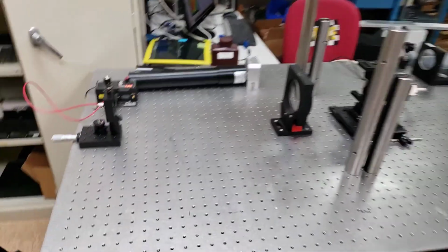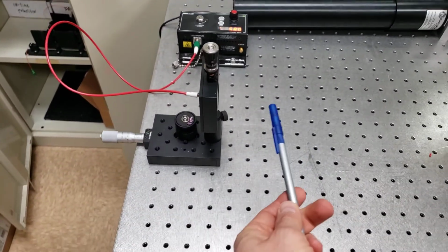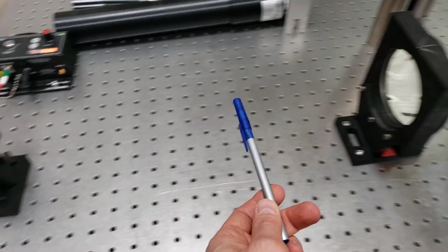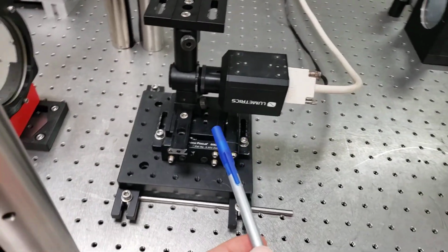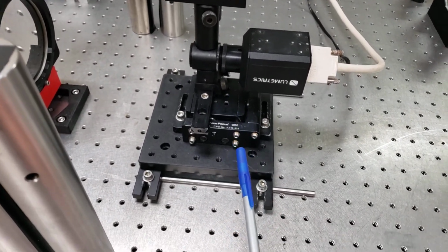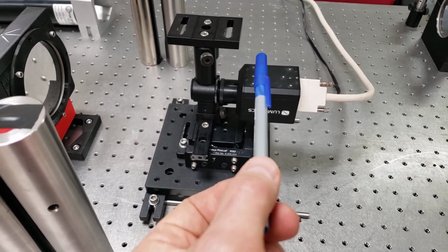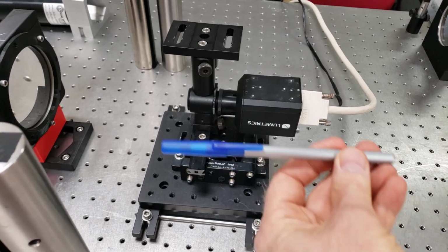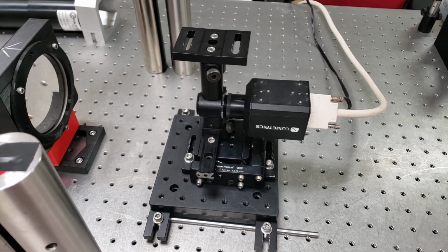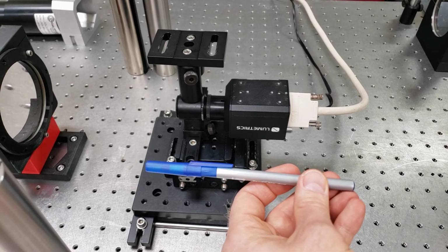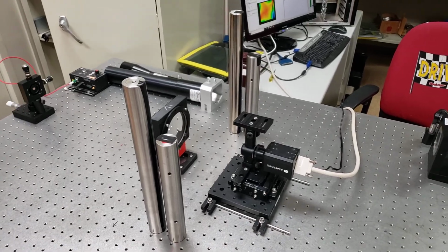Here's the measurement setup. So again, we have the light source and optical fiber. The light is emitted from this point over here, and then it's collimated by this lens. And then here we have the shock-hardened wavefront sensor, and it's mounted on a stage that controls the height, the horizontal position of the sensor, as well as the angular orientation of the sensor. And the sensor has already been aligned in such a way that the axis of the sensor is parallel to the collimated beam. And currently, there is no windshield.